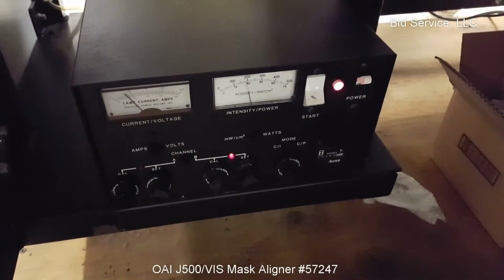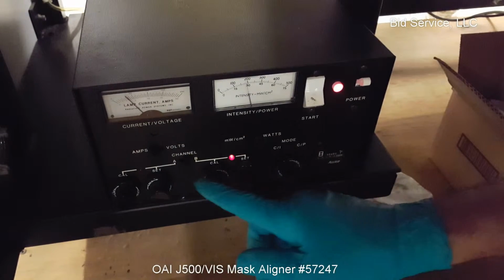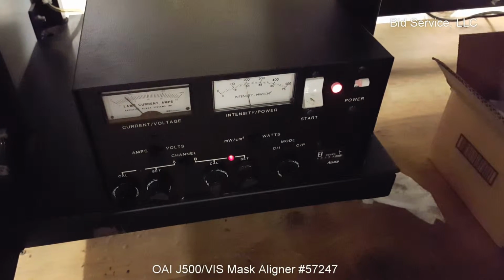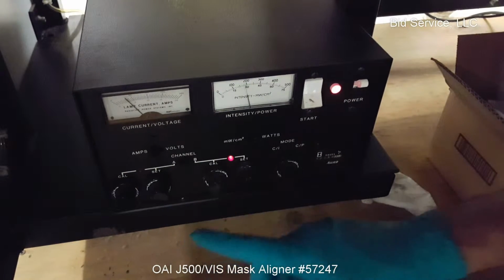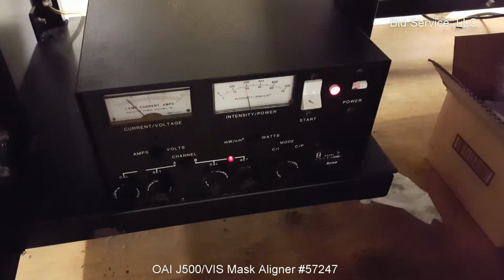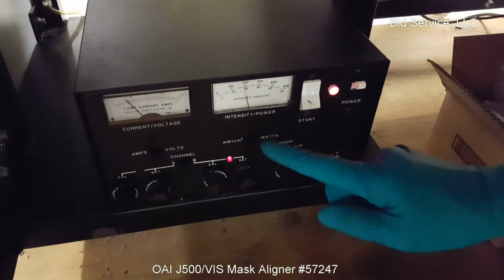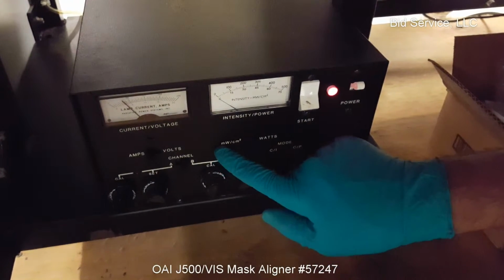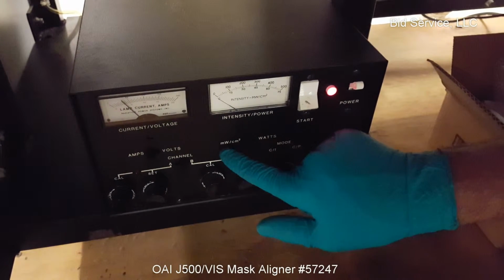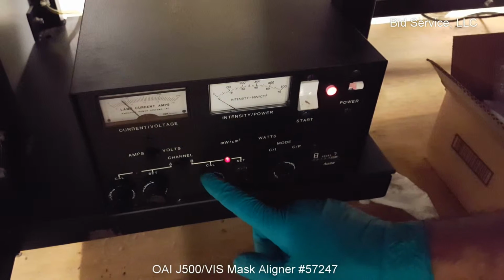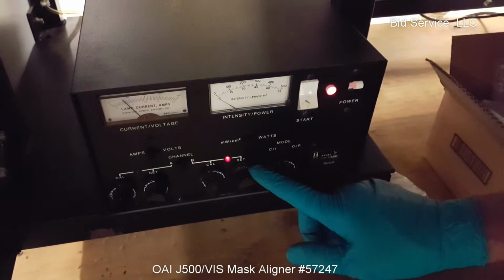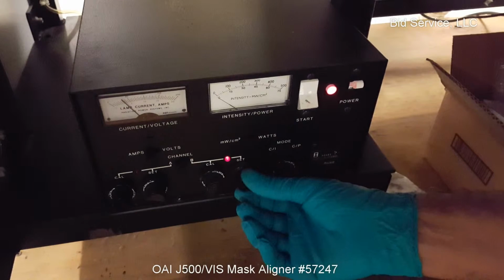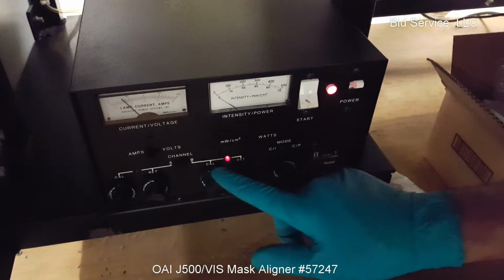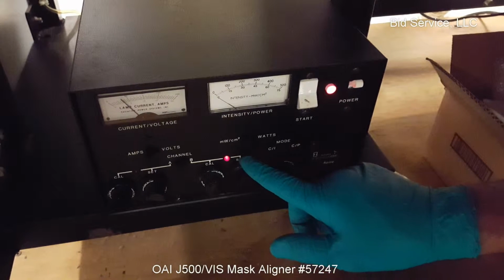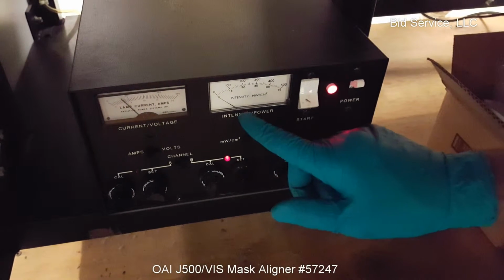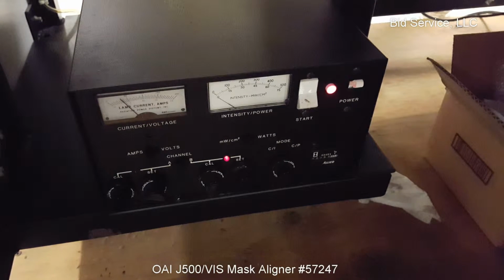And in constant intensity mode, there are two detectors inside the lamp housing for 365 nanometers and 400 nanometers, and the power meter can indicate the UV intensity in milliwatt per centimeter square. There are a calibration part and a set point part, which is adjustable, and these can be turned on only when the lamp shutter is open and the lamp is fully stabilized.